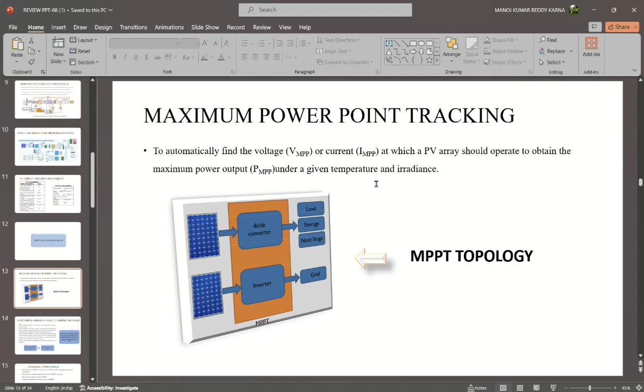Mainly we use the incremental conductance method. Here we use two sensors: voltage and current sensor. The algorithm works by comparing the ratio between the derivative of conductance and the instantaneous conductance. When this equals the instantaneous conductance, the solar maximum power point is reached.